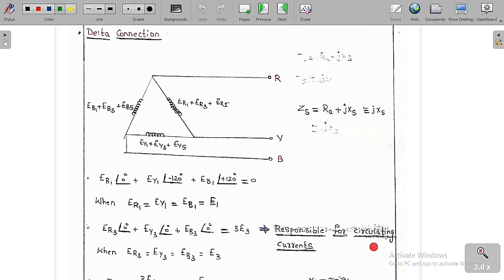This is responsible for circulating currents. Adding the voltages of the fundamental, third harmonic, and fifth harmonic: the fundamental summation is 0 and the fifth harmonic summation is also 0, but the third harmonic summation is never 0, because these are zero sequence components. So the overall voltage is present in the circular fashion, and a circulating current flows because the net voltage in the circuit is not zero. If it were zero, the currents produced by those voltages would be zero. So the fundamental and fifth harmonic components produce zero current in the circular path, but the third harmonic components produce circulating currents in the windings. Third harmonic components are responsible for producing circulating currents - this is a very important point.